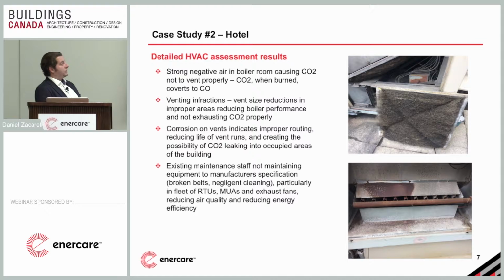Another issue that they had was that they had a makeup air unit in this room as well. That indoor makeup air unit, once we opened it up, looks like it was, give or take, 15 years old, never once maintained. We pulled the filter out of it and it was worse than the filter that you see there in the top right. It was completely plugged. So as that unit is struggling to get the outdoor fresh air through the filter that it can't breathe through, it's actually pulling air from that room through any of the cracks and the holes and the openings in the side of the unit. So that's creating also another large part of that negative air issue.